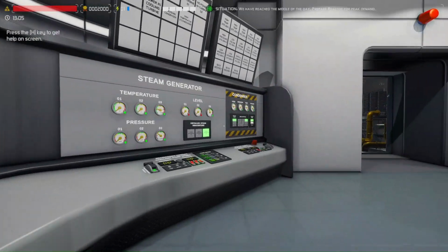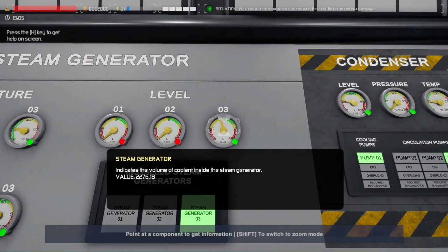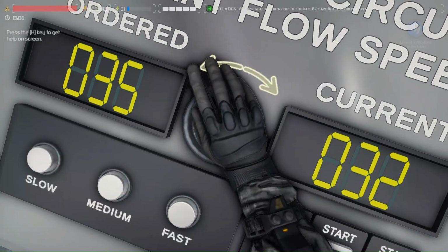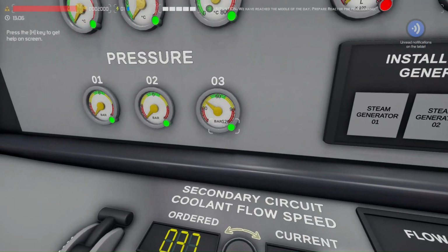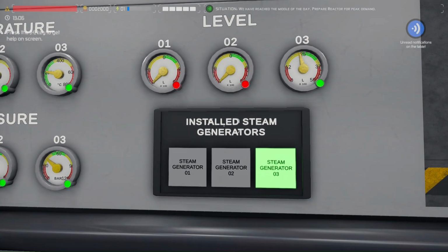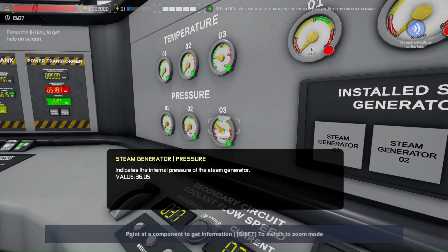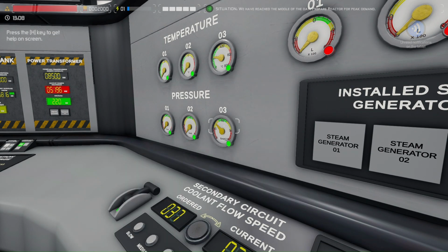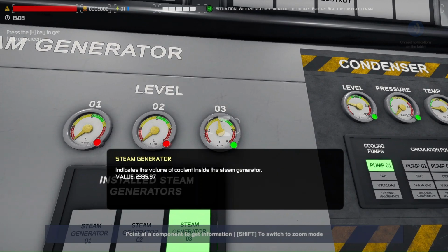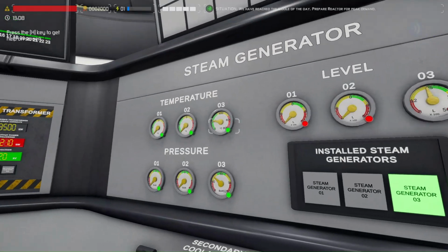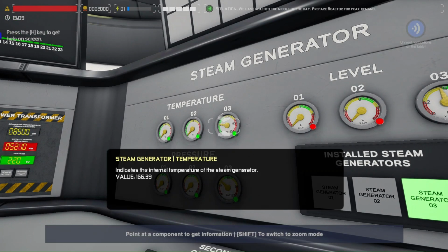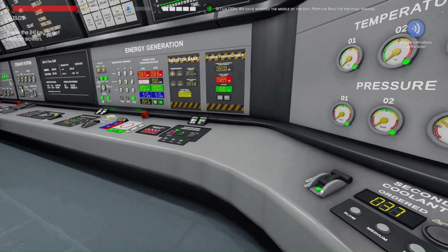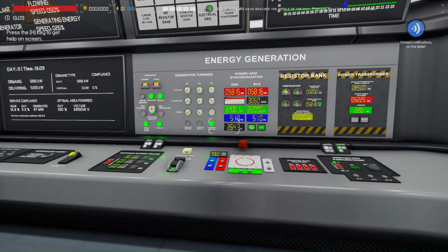Well, when you look at our steam generator, okay, that's a little low, so we can increase this, which will raise pressure a little bit. It'll come down at first because you're adding more cold water to actually raise the level. But eventually this will balance out with the heat input and the steam pressure. So, as you can see, we're at 58.15.